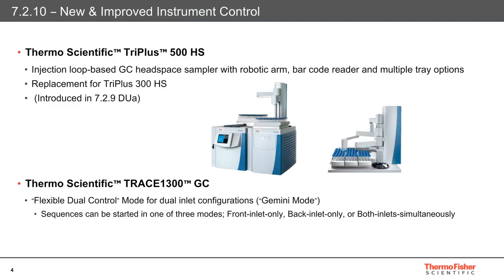This essentially allows sequences to be started in one of three modes: front inlet only, back inlet only, or both inlets simultaneously. In addition to this new feature, the Flame Ionization Detector now supports data acquisition rates of up to 600 Hz to improve application performance.